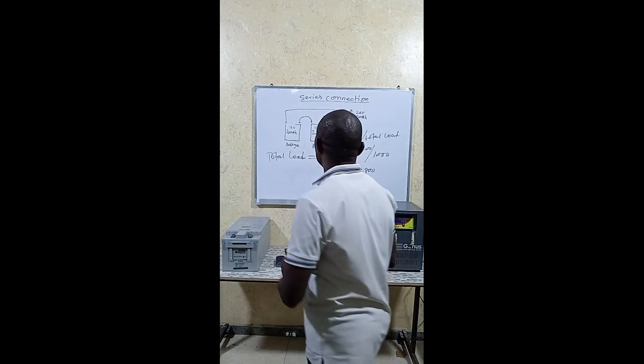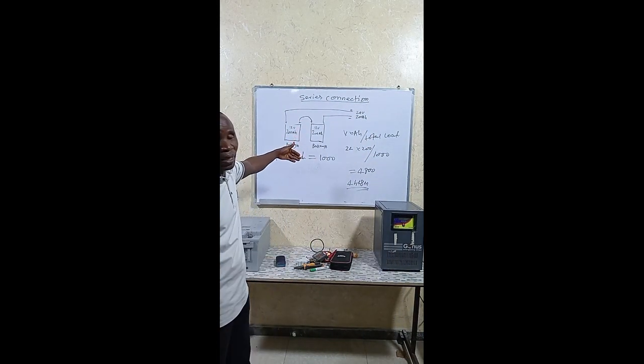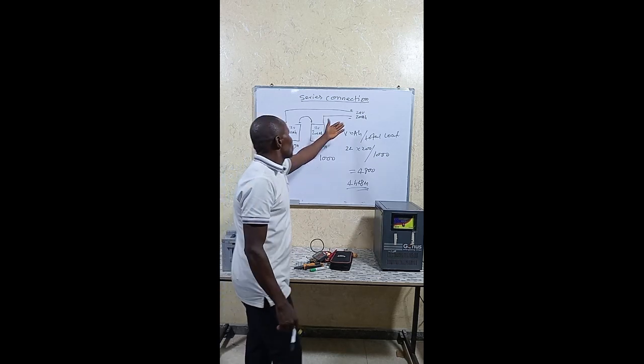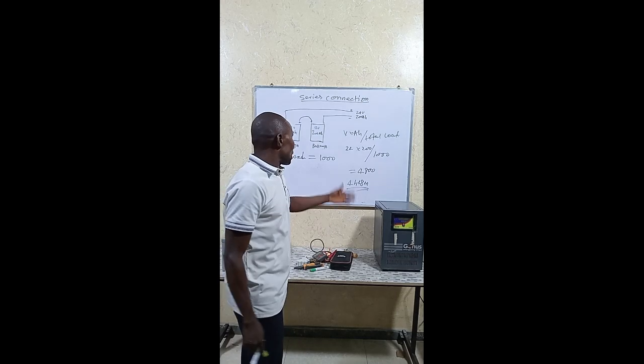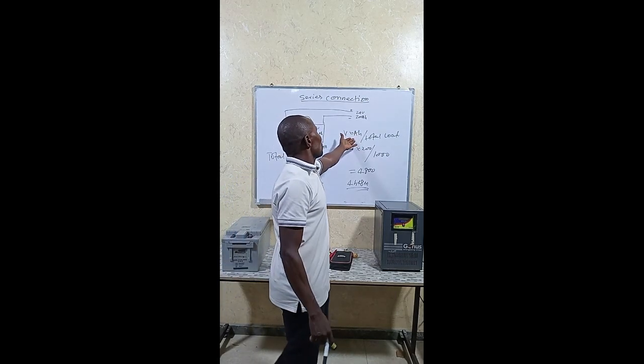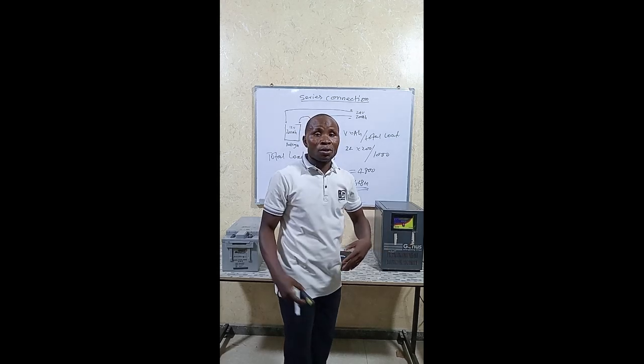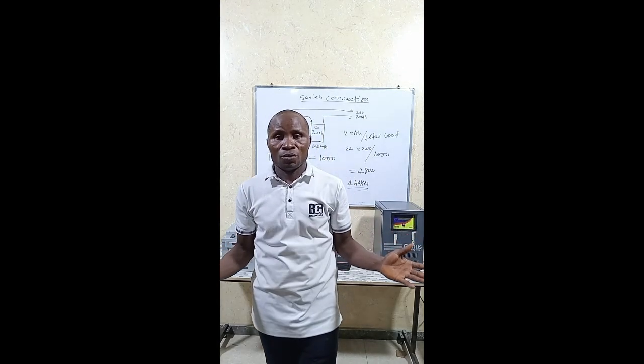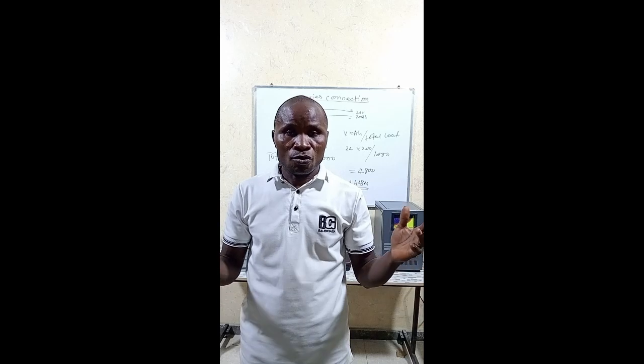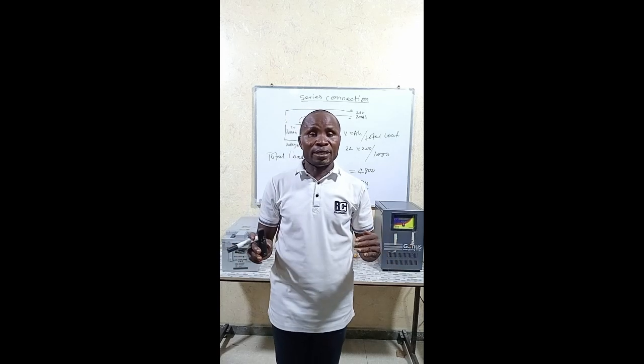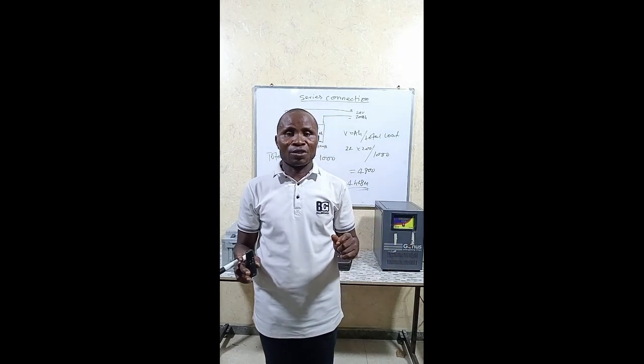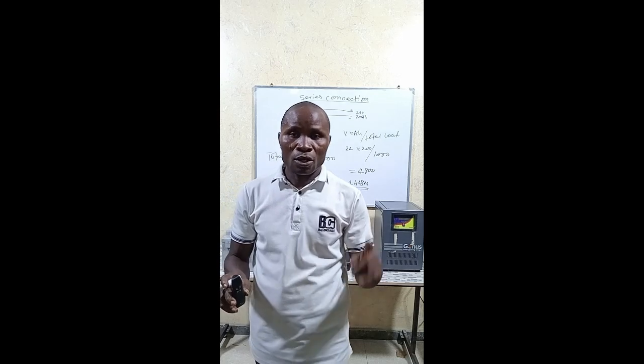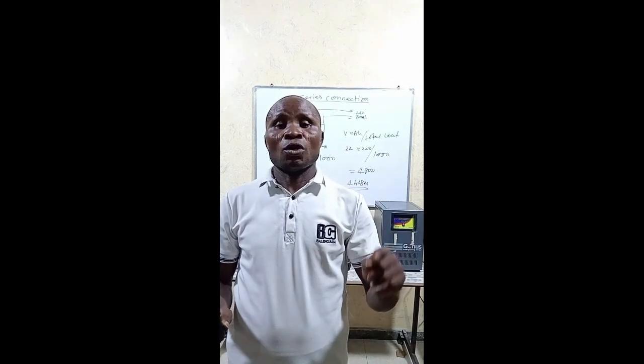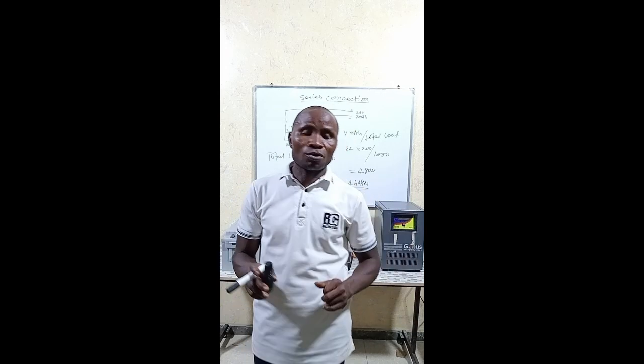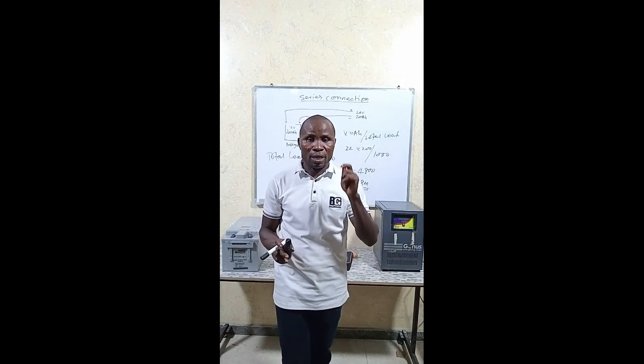You don't need to bother your head anymore, provided you know this one is 24 volts and this is 200 amps. At the end, you just multiply the voltage by the amps hour, divided by the total load, and you know the hours it is supposed to carry you. Anything short of that, call your professional technicians to come and check why it is not carrying you, why the battery does not last.